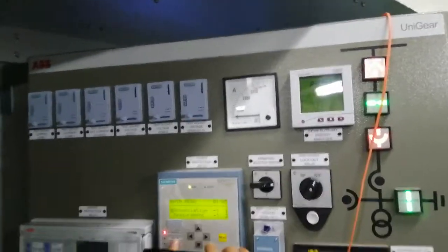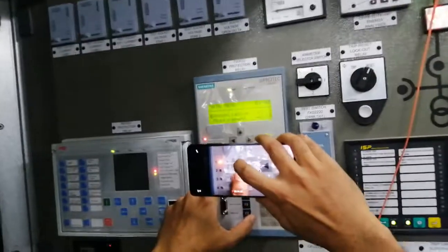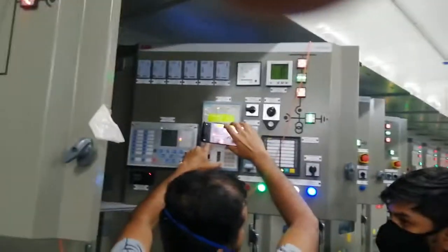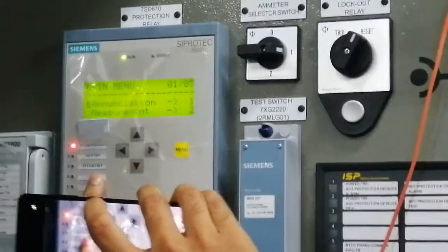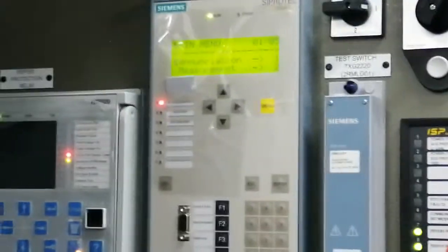The mechanical trip is actually for the transformer, but this will light up on the mechanical protections of the transformer, also on the 11 kV breaker failure, and also on the ground fault protection that I showed. So this signal is a summation of three signals. Let's check one by one. So we are checking the intertrip from 11 kV to 132 kV side on different protections.